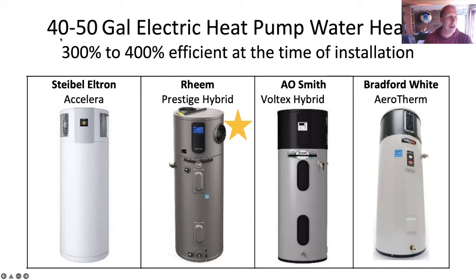Now Wendy asks, what about a tankless water heater? So the tankless water heaters rely on really concentrated energy in gas. They bring in tons of explosive, high potential gas, and they have a small amount of space that they burn it in. Heat pumps don't work that way, they sort of filter feed a relatively not heat-dense amount of heat out of the air, so they work slowly. By comparison, a gas on-demand water heater might produce 80,000 to 120,000 BTUs per hour, British thermal units of heat, versus a heat pump water heater, which is about 4,500.